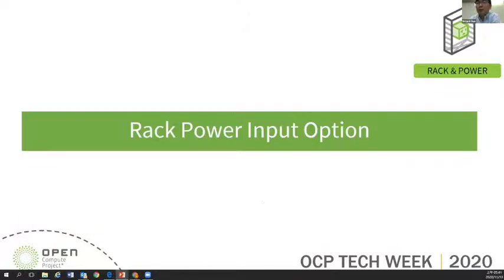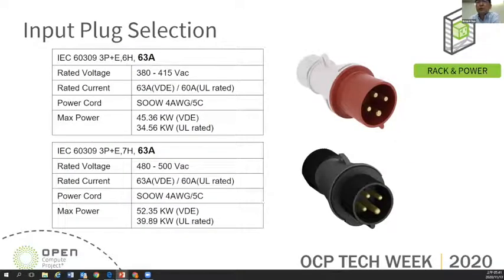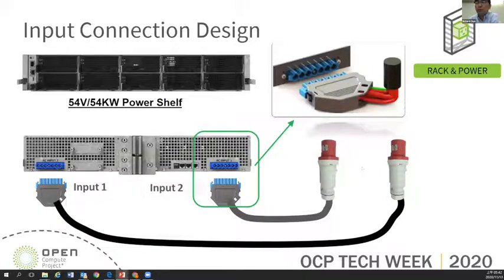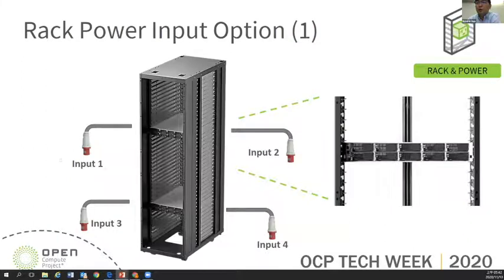So for the input of the power, the first thing is we need to select a suitable input plug. So we find the IEC 60309. They have some 63 amp plugs, 2 kinds. One belongs to the 380 to 415 volt input. The other one is the 480 volt input. We can utilize these 2 power cords as an input. And then, similar to the V3 power shelf, we just use the pluggable OCP type of connection to connect with the power shelf. You can see each power shelf can have 2 cable flaps. So for the whole rack, they have 4 input cables connected with the input.